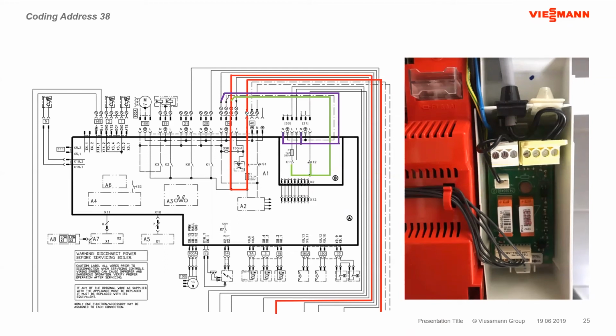Once that power goes through, we are going to basically power up or energize or have 120 volts at these relays. So there's the K12 and the K11 relays. These are switching relays on this board, and they are switched off of a 24 volt DC signal. So something a little bit different here.